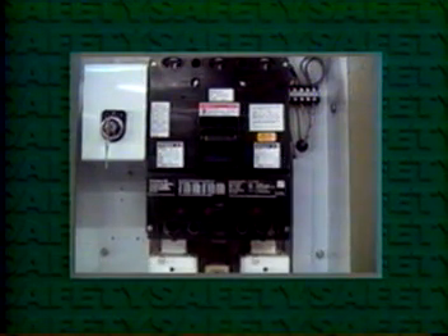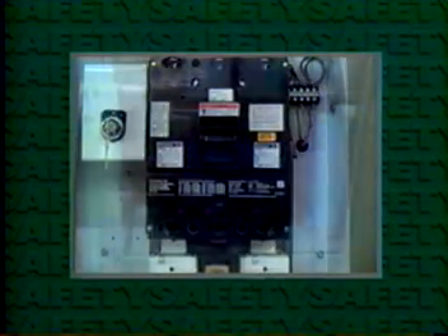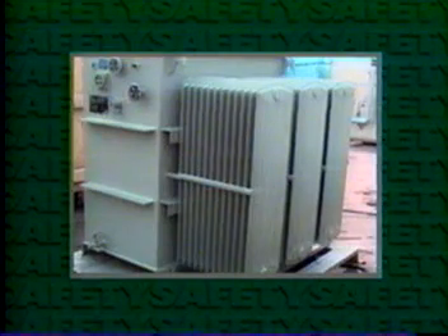Ultra-fast acting solid-state circuit breakers on larger systems and current-limiting reactors and quick-acting circuit breakers on smaller systems provide protection against component failure and major line disturbances. Secondary isolation from the incoming power utility line may be provided through an isolation transformer located between the inverter and the furnace. Primary isolation may be provided by locating a transformer between the incoming power line and the inverter.